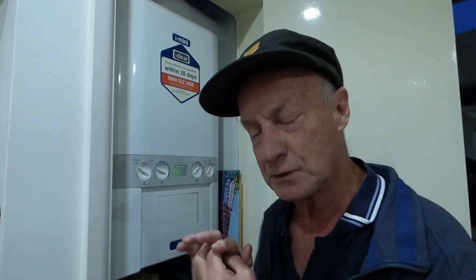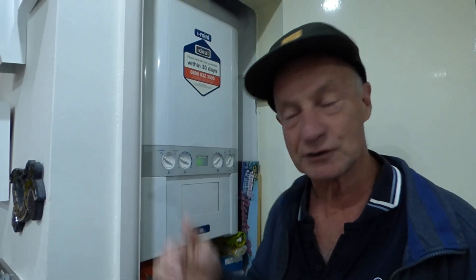There is a safety outlet on there, so people need never worry about the pressure being too high — it's not going to blow up. The pressure relief valve is there for a reason. If you look at your boiler, you'll probably see there's a pipe running outside from your boiler — maybe going down the wall or out through the wall — and that is a small pipe to take the water away should the pressure relief valve blow at any time. If you see there's been water coming out of that pipe, then you know you've got a problem. That is invariably the giveaway.